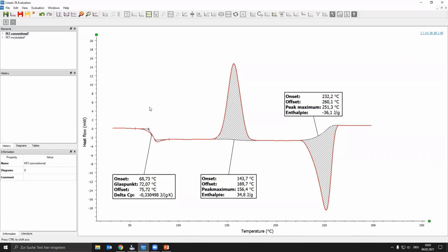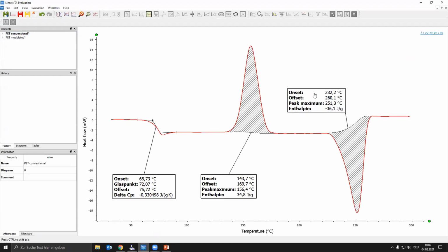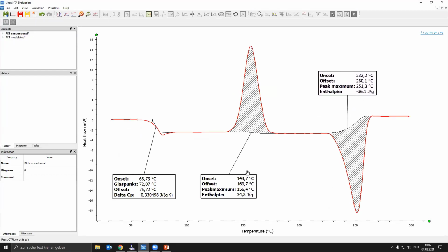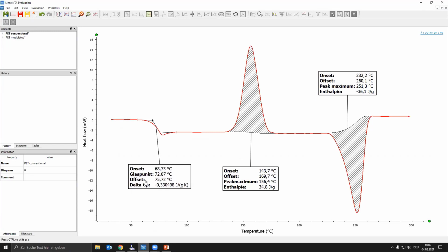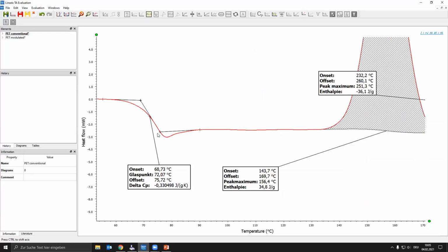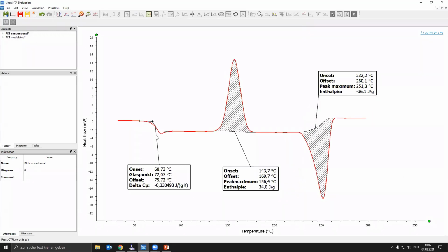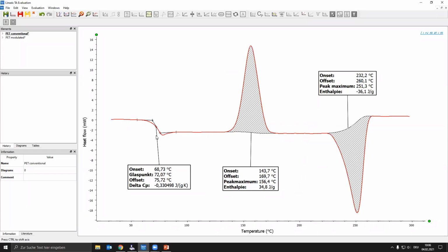At first, here we can see a PET measurement with conventional DSC. So I already explained, at first, we can see here for this sample the Tg. And what we can also see here is the relaxation peak. So especially to evaluate your Tg with intersection, the hysteresis peak or the relaxation peak will affect the result for your glass transition. So here, again, one of the advantages of the temperature modulation, we can split it into reversing and non-reversing parts. Next, of course, we can see here the recrystallization peak and the melting peak with the line due to the lower Cp values.